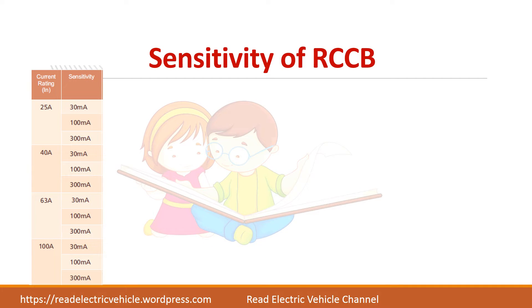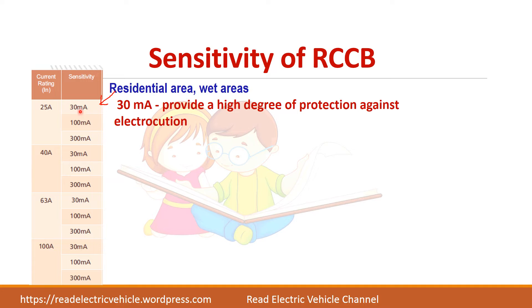The sensitivity level depends upon the application. If you are in a residential area or wet area, it is always advisable to use a lower residual current setting. So 30 milliamps provides a high degree of protection against electric shock. Because in residential areas, the safety of human persons is more important and the leakage current will usually be less, so we always prefer 30 milliamps in such cases.